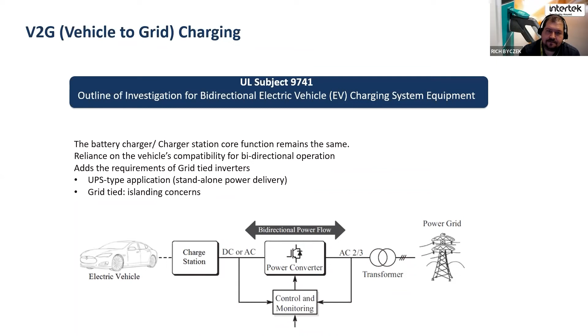Battery integrated EVSE. We've seen this since the advent of CHAdeMO systems here in North America, where you want 25 or 50 kilowatt charging power but don't always have that much grid power available at the location. Instead, you have a system with a much lower power level used to charge a separate offboard battery—the center box in the image—at much lower than 25 or 50 kilowatts. When a vehicle plugs in, that battery is used to source the 25, 50, or higher kilowatt charging rate.